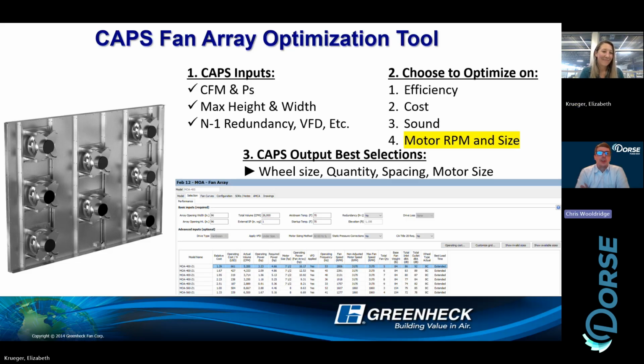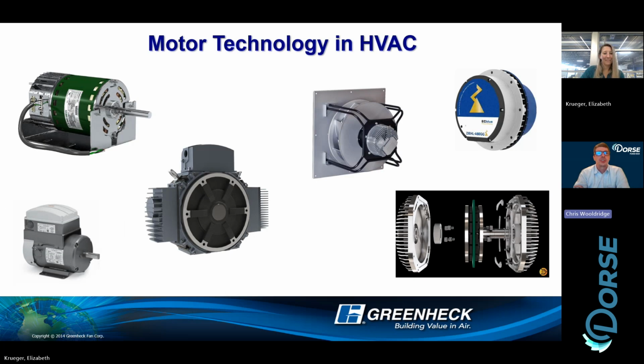No, I mean that motor, I've been lucky enough to see one in the testing station, and when you see what a normal 7.5 horsepower motor looks like compared to the new one, it's remarkable how much smaller it is, and I think a little bit lighter. To be fair, I don't know if I picked it up, it just looked lighter. And again, the smaller it is, the less that's taking up air, right? It's less impedance on the airflow, less pressure resulting in the system.